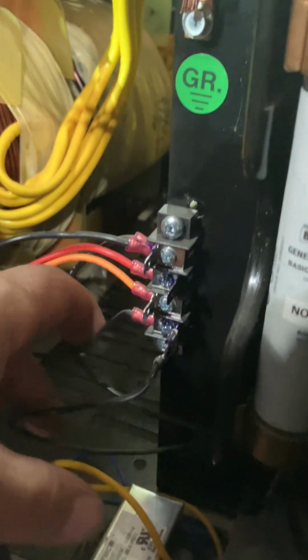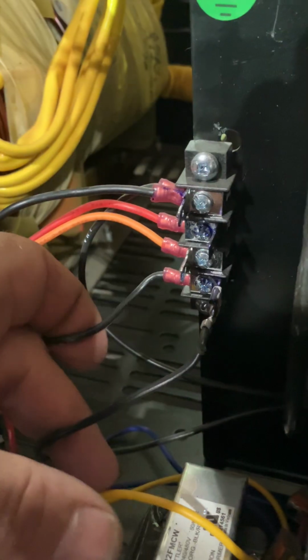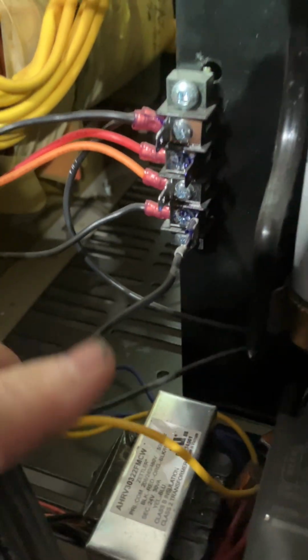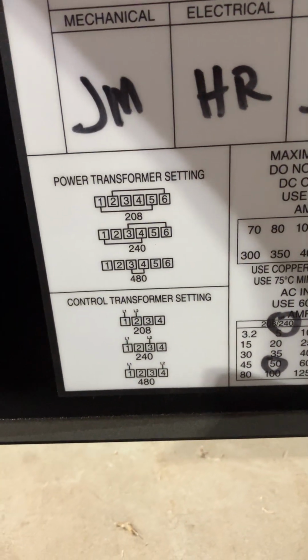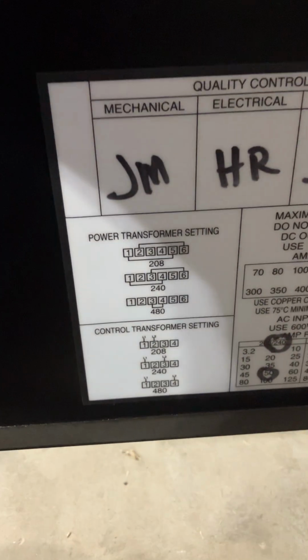There it is, and that is coming from the transformer. This is the lead, right here, from the 480 tap on the transformer. And we're tapping from there to the contactor, feeding on into the machine, into the control board there that we're looking at the back of right now. Here's the front of it. Again, whenever you hook up a piece of equipment, look for all available information, because you're not automatically going to know how to hook it up. Be sure and check so that you can hook it up correctly.